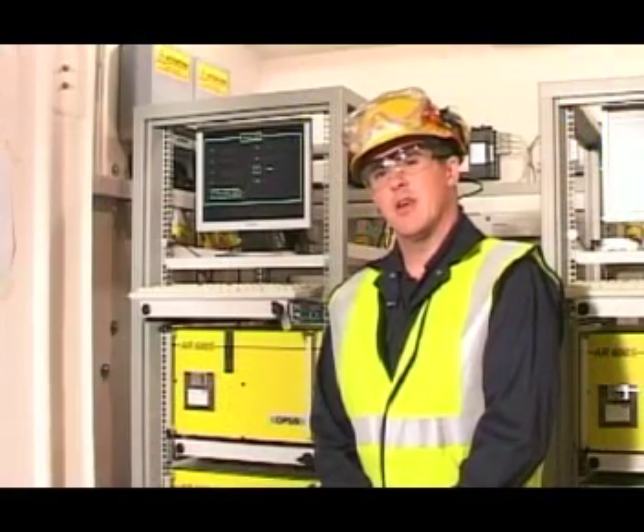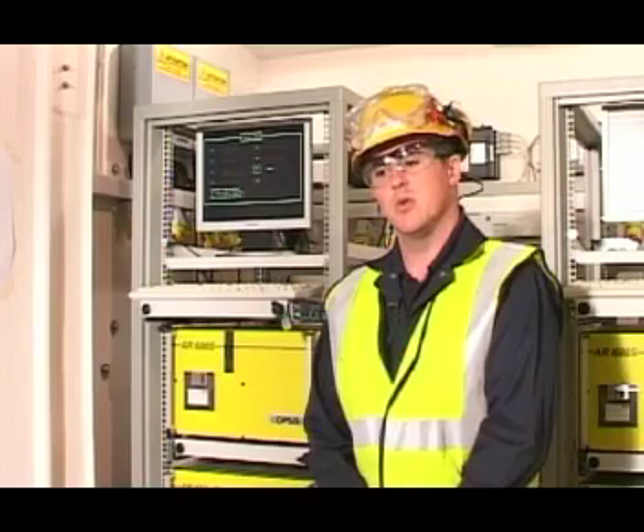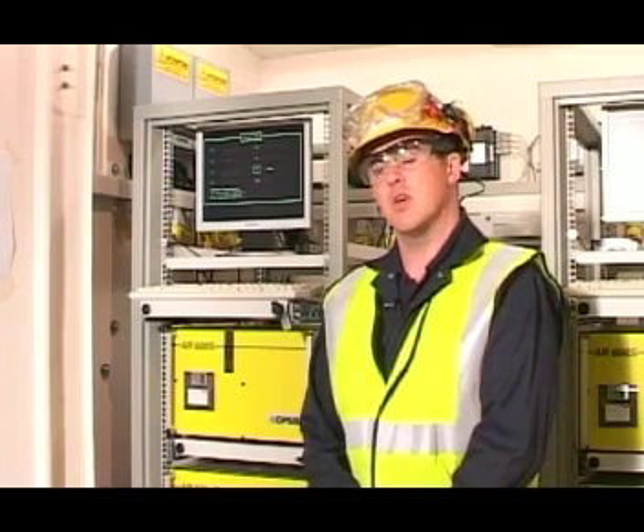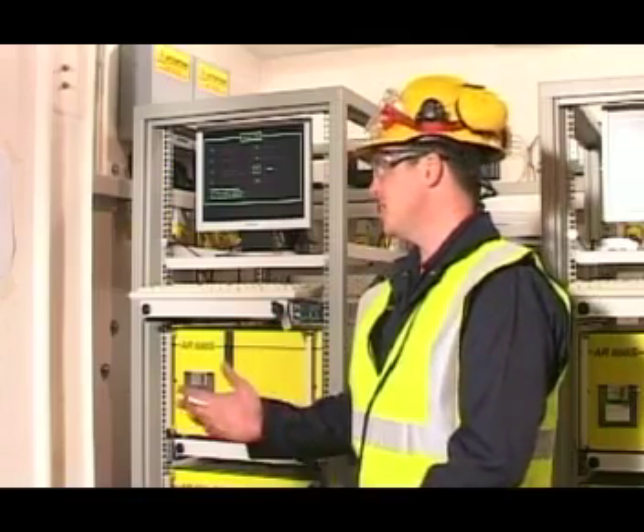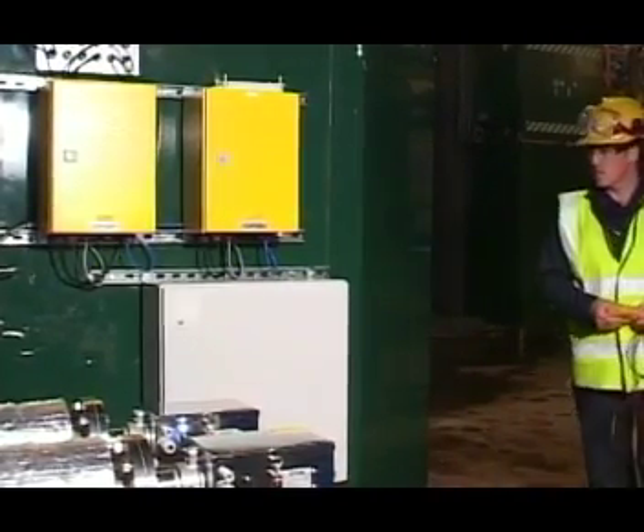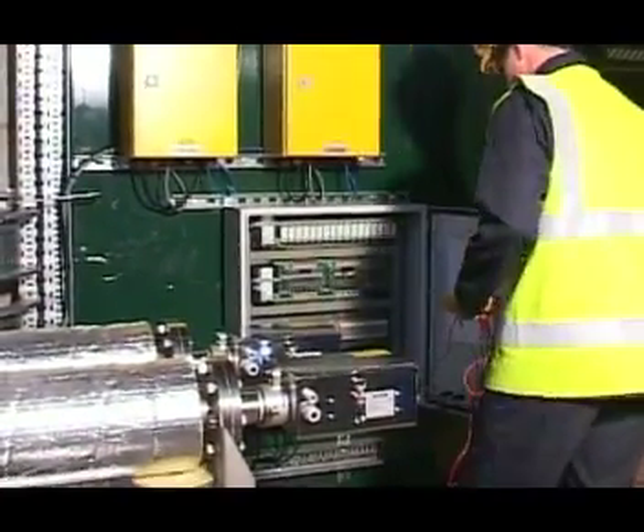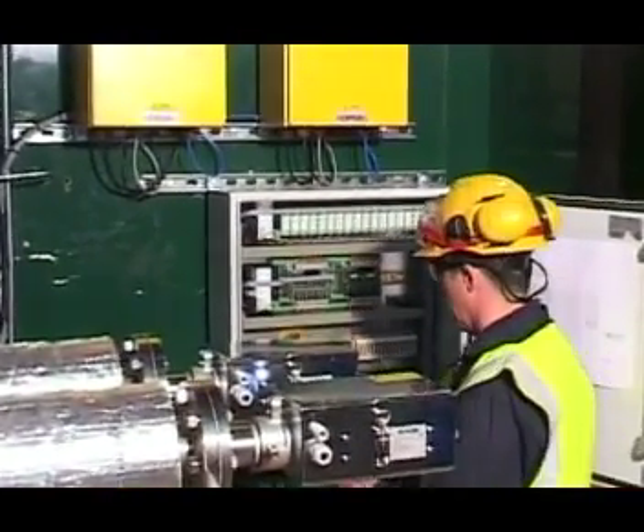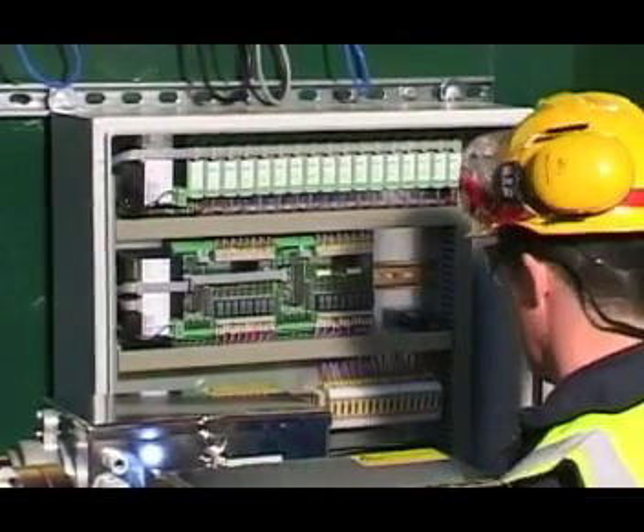Enviro Technology was on a tight deadline on this particular installation due to the requirements of the client. The client always shuts down for a 2-week period in the last 2 weeks of August, and the system must be installed, commissioned and fully tested during that period. The client cannot start the plant unless the CEMS system that you see was fully tested and ready to go. Because of this, we decided to work with 2 other contractors, one electrical contractor and one mechanical, to help Enviro Technology with the huge amount of cabling and also the mechanical requirements of this job. Things like all the pipe work that you see coming down from the duct work.